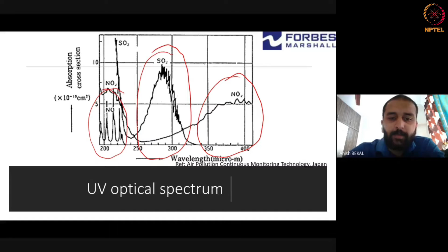Right. So if you look at this as it is, what you need is a particular source which looks at the spectra in the NO2 region, which again looks at the spectra in the SO2 region, and which looks at the NO region. Okay, so when you see that directly, the first thing that comes to your mind is that you need to measure these spectra and basically sum these spectra. You have to find a correlation between the absorption that has happened and the concentration. That requires a certain amount of calibration. And then also what is important is that in the region where SO2 has spectra, there is also spectra from NO2. Okay, so we need to compensate the value that is generated from the SO2 spectra in order to remove the interference that is happening over SO2.